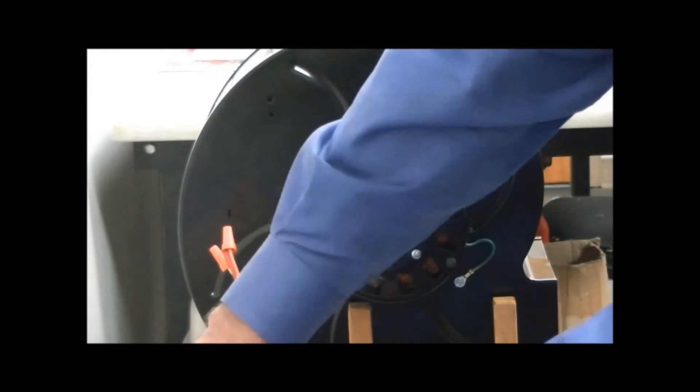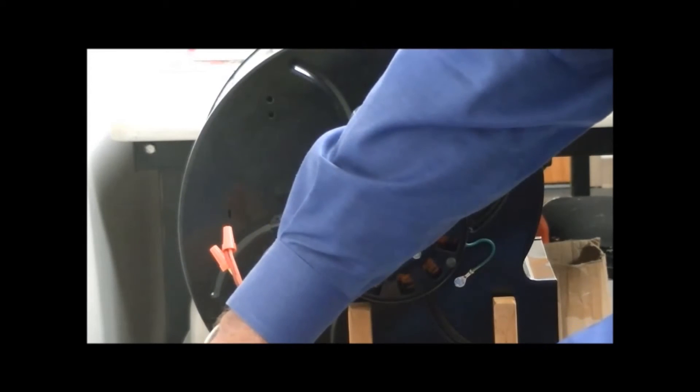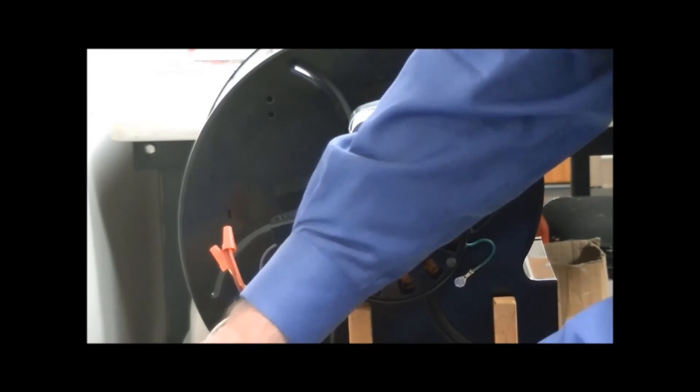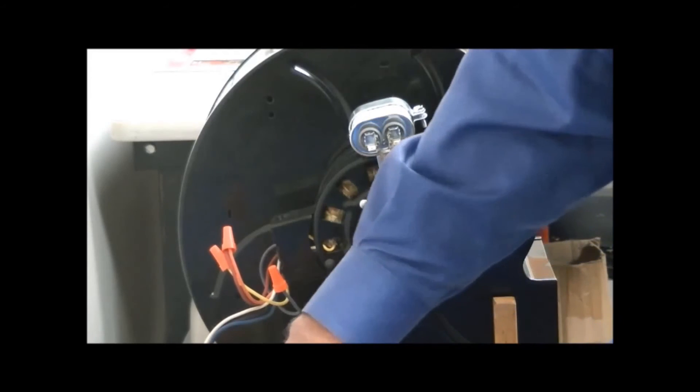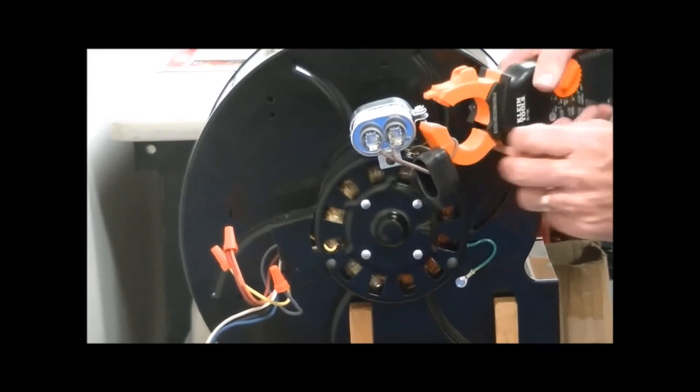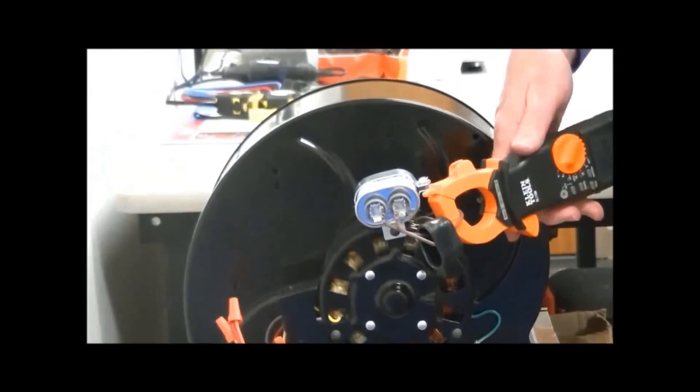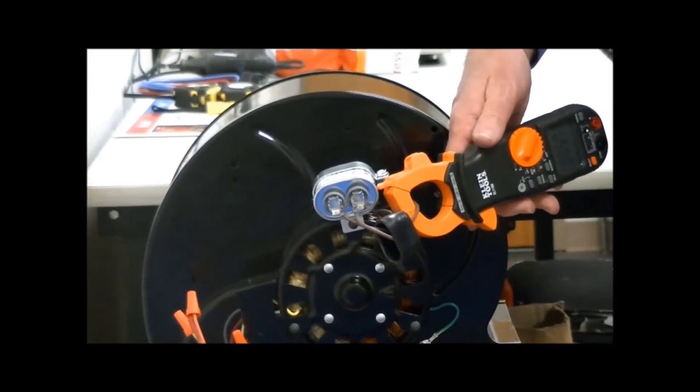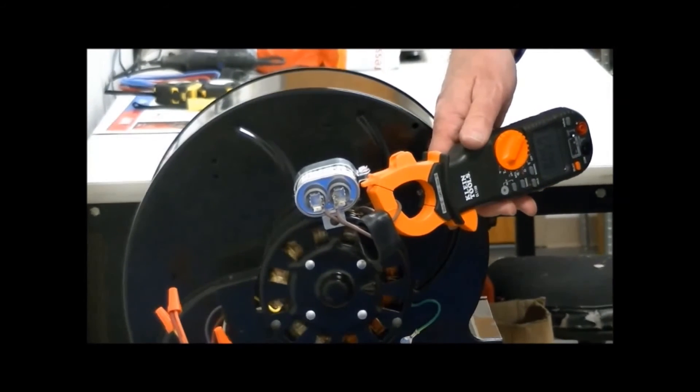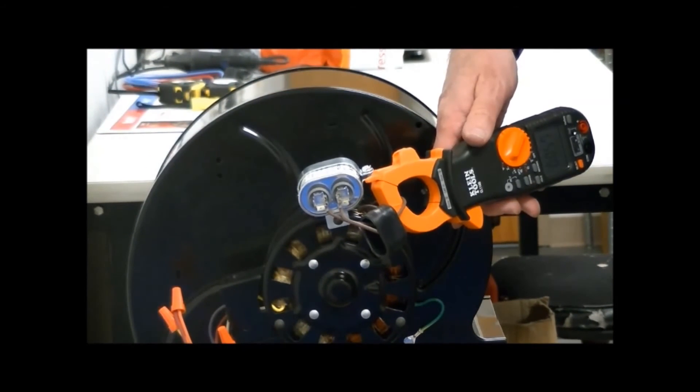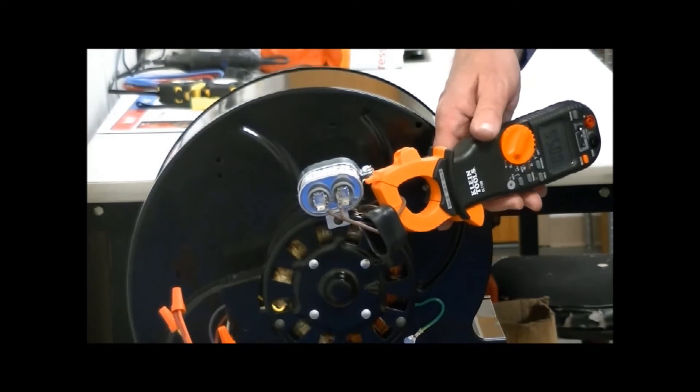Now we'll check the capacitor amps. Set that on amps. Using our clamp, put it over one of the terminals. That will give us 0.57 amps.